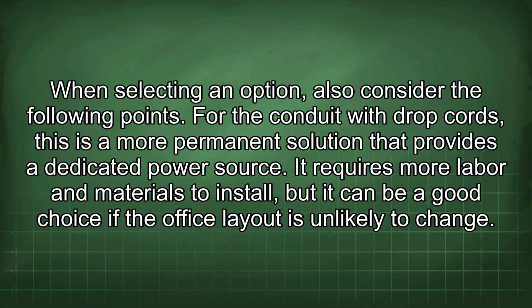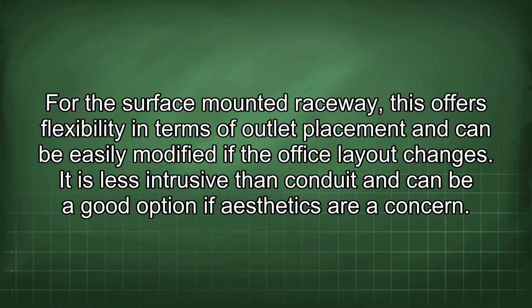When selecting an option, also consider the following points. For the conduit with drop cords, this is a more permanent solution that provides a dedicated power source. It requires more labor and materials to install, but it can be a good choice if the office layout is unlikely to change. For the surface-mounted raceway, this offers flexibility in terms of outlet placement and can be easily modified if the office layout changes. It is less intrusive than conduit and can be a good option if aesthetics are a concern.